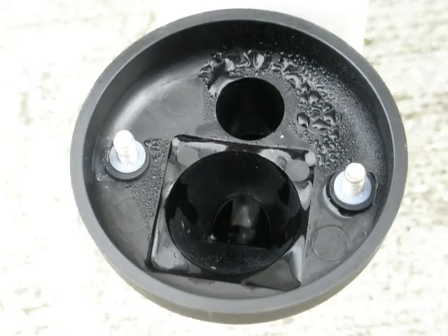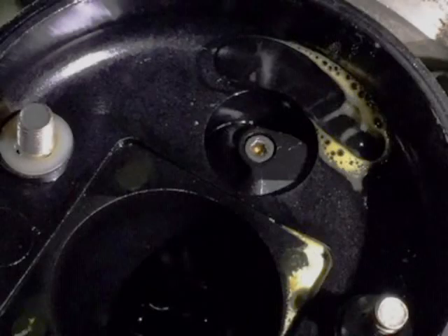With the detector head removed, check the detector base. Excess oil in the base can be wiped off. Oil in the inlet, or outlet holes, can be cleaned by blowing compressed air down the holes. The presence of foam, or other deposits in the base, could indicate water or other contaminants in the engine's oil, which may require further investigation.